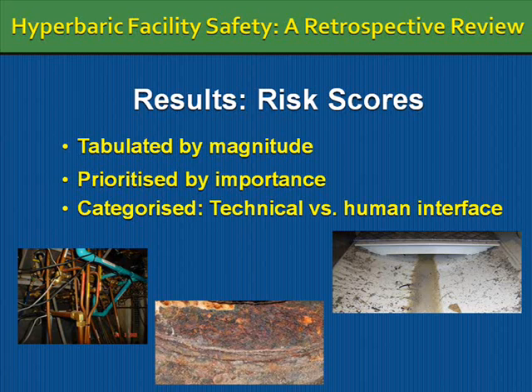Well, it actually affects fire, because if there's oxygen in that pipe and you're leaking oxygen and you get a spark somewhere, and I assure you in the control panel there's lots of dust, you can have a fire. You can leak gas without knowing it, and by the time you come to switch over your gas on the chamber to give the patient the other gas, there's no gas left in the system.